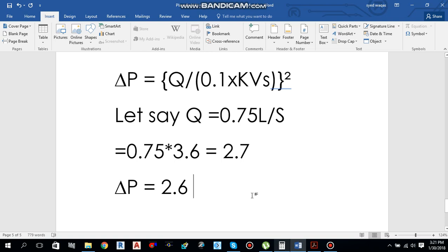Let me tell you why water balancing is important. Water balancing is important to ensure that the chilled water system delivers correct flows to all terminal units in our HVAC circuit, so that our control valves work properly, which results in the correct output of energy to the space. So this is very important. This is how you can check how many turns we have to open the DRV for water balancing in terminal units, fan coil units, and air handling units.